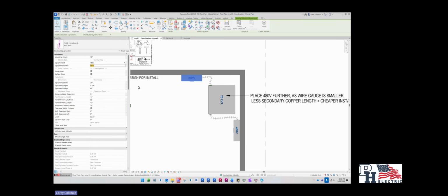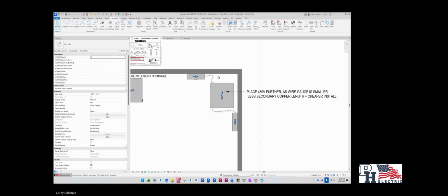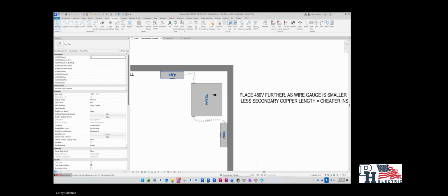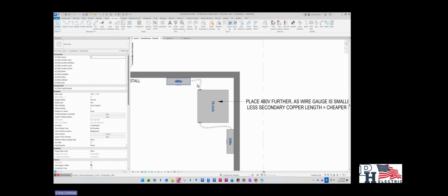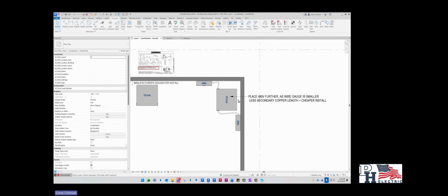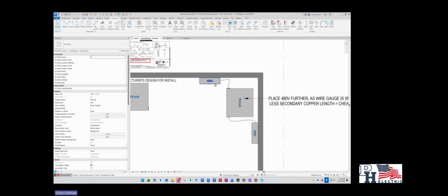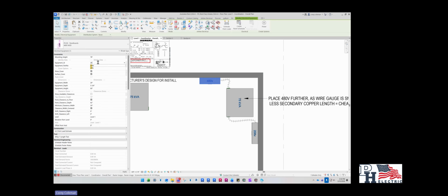Where this one was the 480 volt panel, and this was the 208 volt panel. If you're stuck in a tight spot, this is not really going to be the end of the world, but it is a little bit of a help on the install and the pricing of the gear. So try to work it if you can with the 208 volt panel closer than the 480 volt panel.